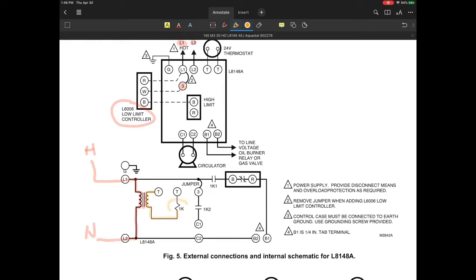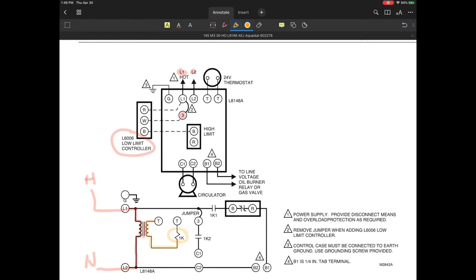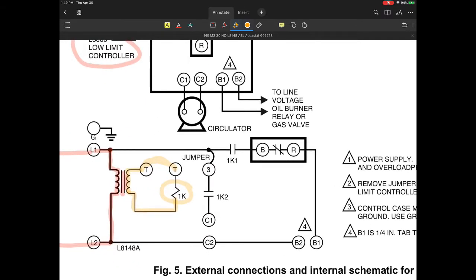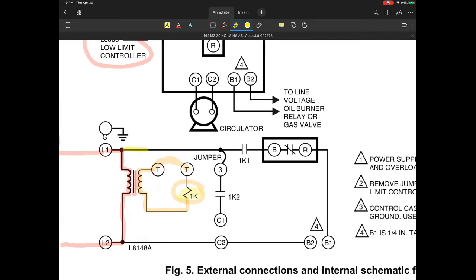Now, on the low voltage side, that 24 volts, you'll notice, is doing nothing more than energizing this 1K relay. So when there is a heating demand, and up on top here, you'll notice how they're showing you this thermostat. Any 24 volt thermostat that is designed to work with 24 volts is doing nothing more than completing this circuit between T and T, is really what they're trying to do. So when we complete that circuit, we're going to power up this 1K relay.